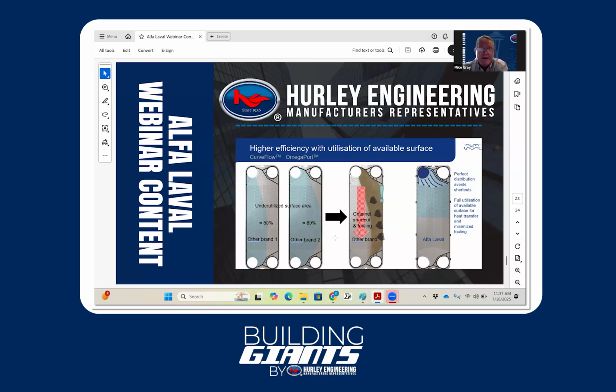Making sure pressures and temperature readings are really helpful to know if you're off of performance or have an excessive water pressure drop, which are both indicators of excess scale. But sorry, Mike, keep going. No problem. Gauges on all the ports is really essential, or at least a way you can check, whether infrared or something, to see what your temperatures are coming out. Just good practice. Okay, next.